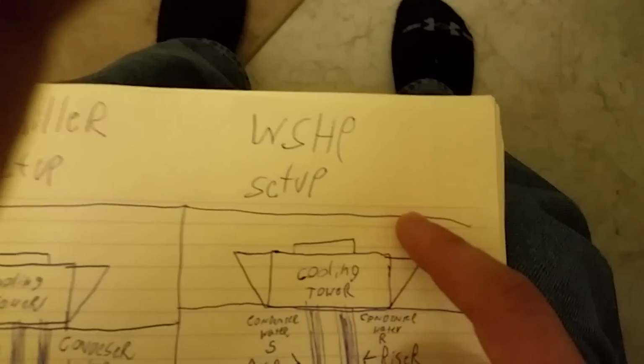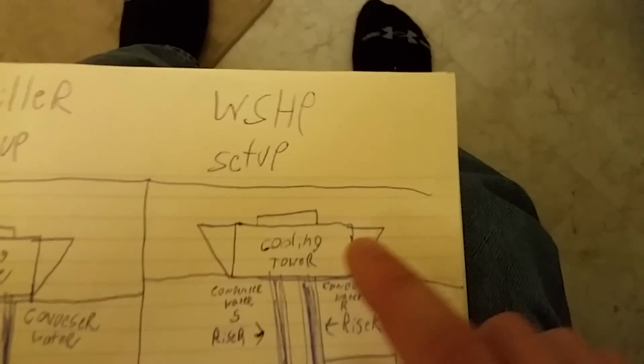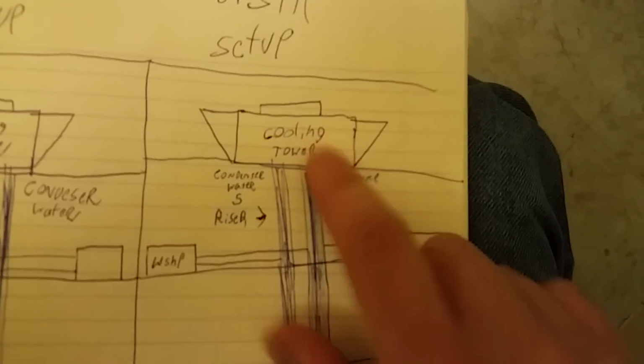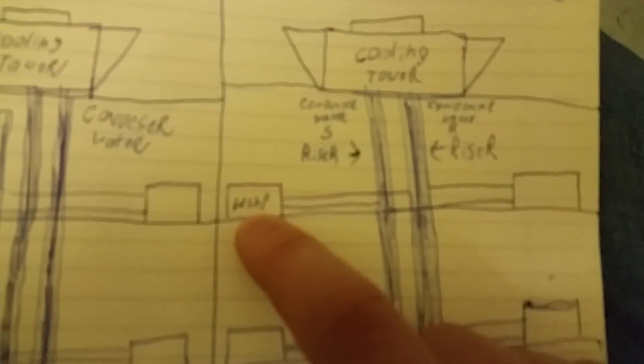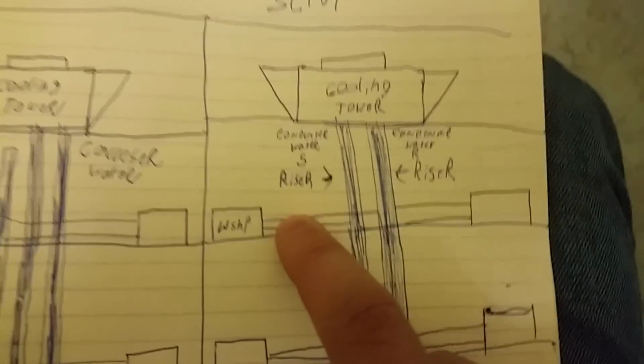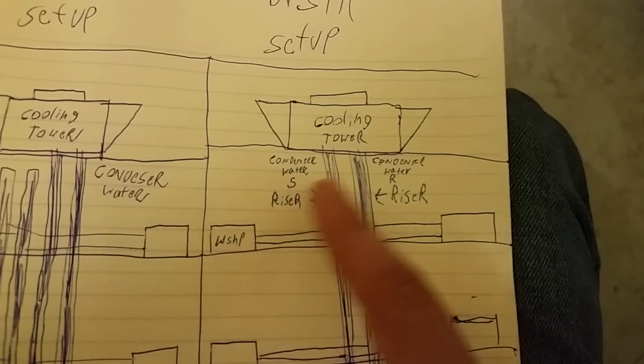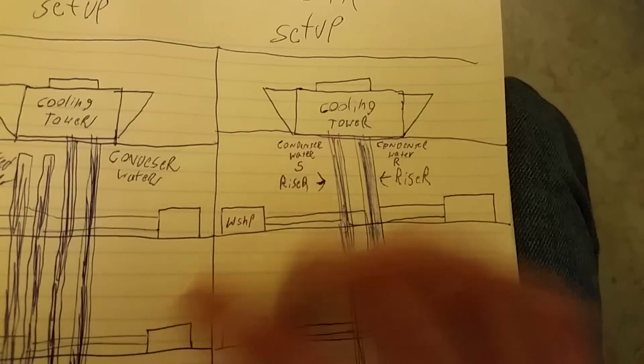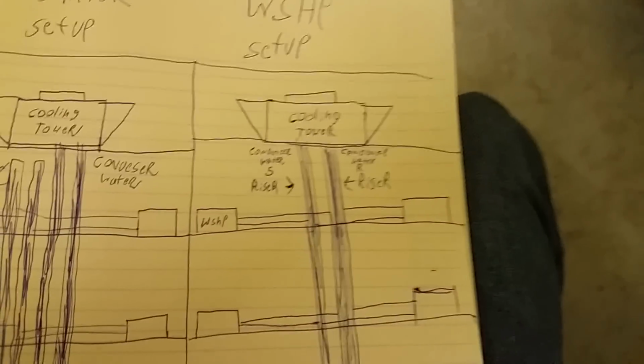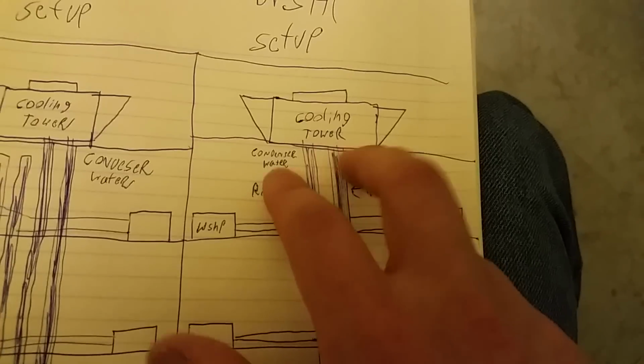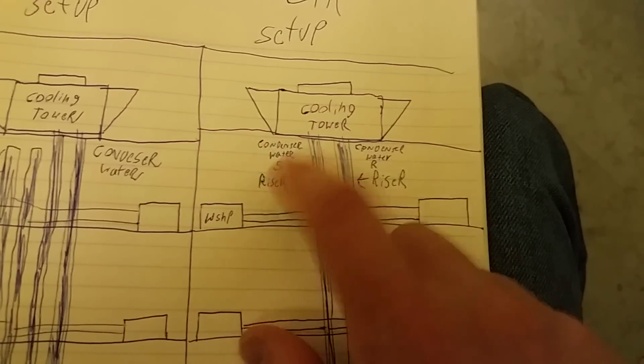So let's start with the water source heat pump setup. Obviously, we have a cooling tower. Now, each floor has a little water source heat pump unit, which the compressor is cooled by water. Now, most buildings have console units, but some buildings will have ceiling units and console units and all that good stuff. We have our condenser water risers, supply and return, going to the tower, coming back. Obviously, the pump is in the basement.